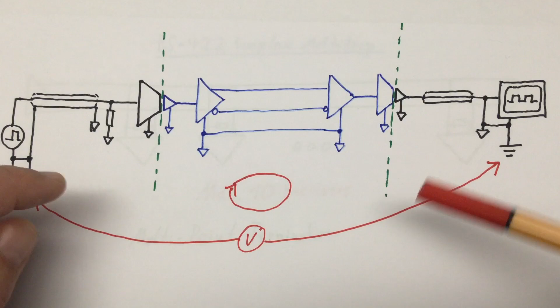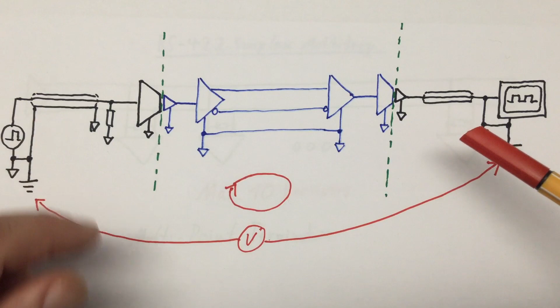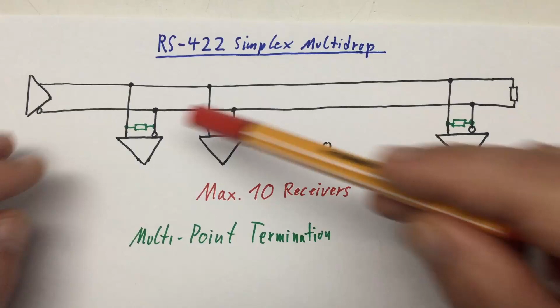However, to solve these two problems, you don't need to isolate both sides. It's completely sufficient to either isolate just the transmitter or the receiver. But you have to be careful if you use multi-drop, that is one transmitter and several receivers. In that case, you have to isolate each and every receiver. You don't have to isolate the transmitter, because if you isolate the transmitter and not the receivers, you again can have potential differences between the different receivers, and you can also create again ground loops between the different receivers.